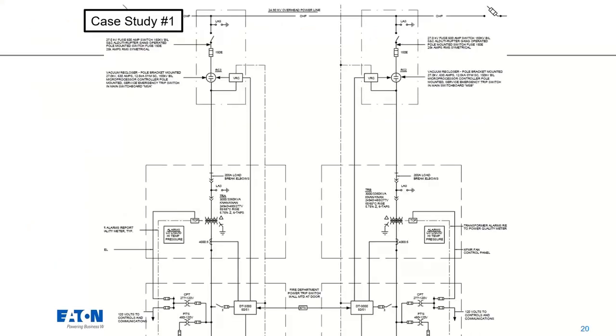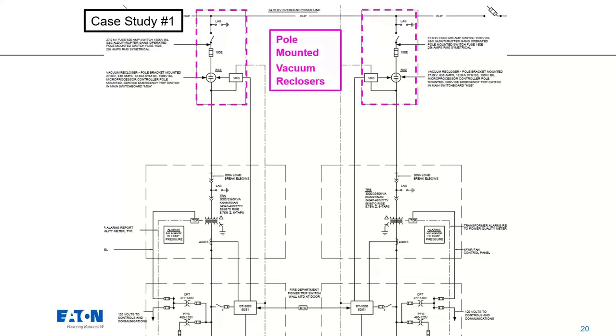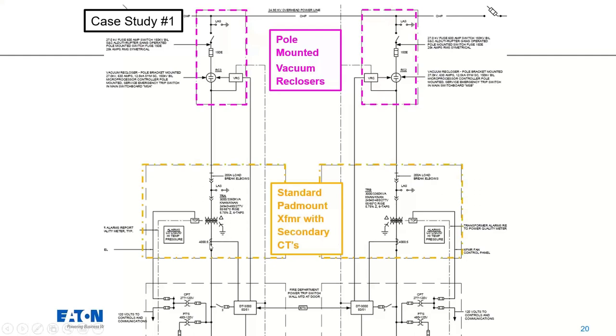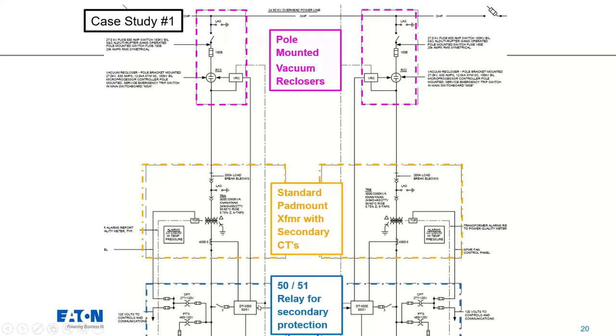So looking at our case study here, just a single line diagram. In this case, we've got pole mounted reclosers that are feeding the transformers. We've got our standard pad mount transformers with our secondary CTs, and those are critical to the discussion here. And then below that, we've got our 50-51 relaying feeding our low voltage gear, our draw out switchgear, that's going to be the zone that we're analyzing right now in this case.